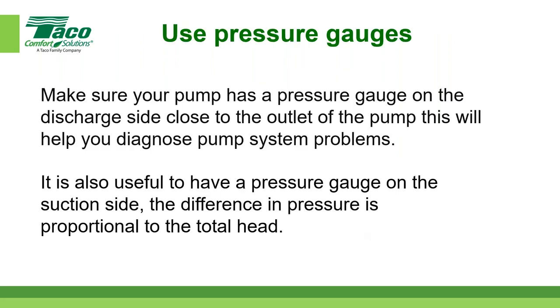The other thing Rich and I recommend, and you've seen it in one of the pictures, is make sure your pump has a pressure gauge on the discharge side, right? We got that little piece that you could tap right into the tapping on the pump itself, as you've seen in that picture. This will help you diagnose pump system problems. It should be there. Most applications, most mechanical rooms, I see it. You take it as just a norm. But please include it in your details, right?